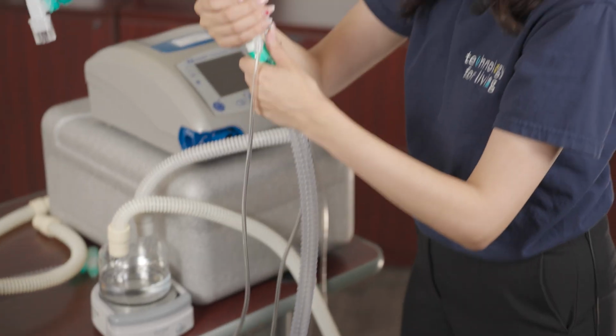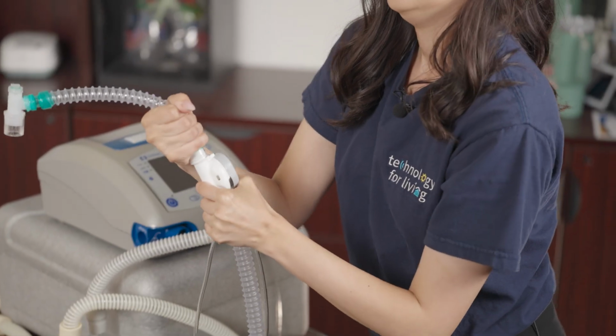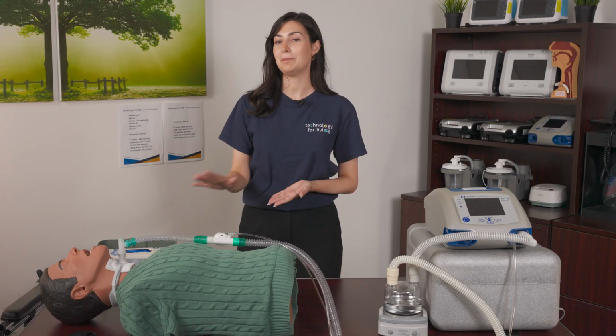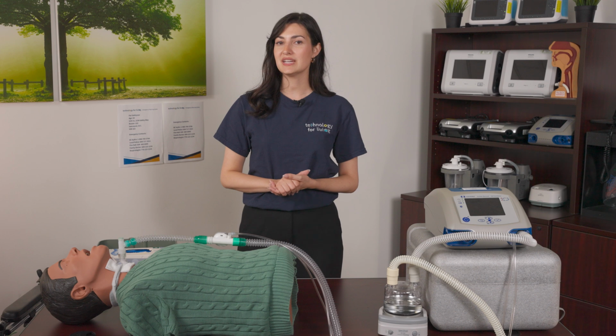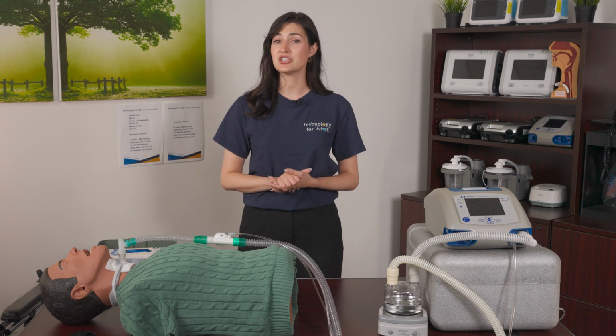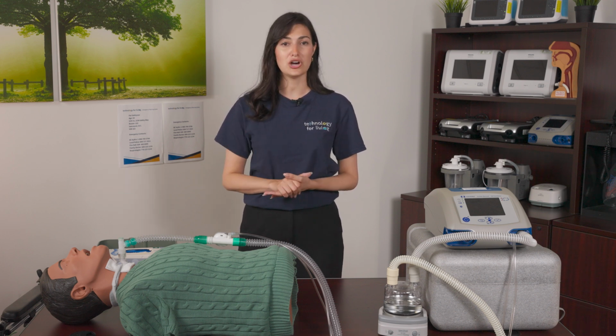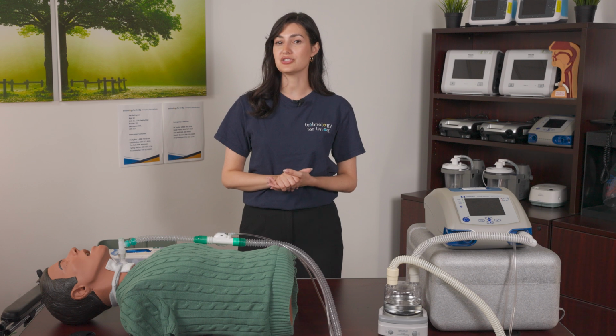I've addressed all the issues in the circuit, so I can now complete a circuit test and try the ventilator back on the member. Once reconnected to the ventilator, if the situation is resolved, then great. If not, try taking a brand new full circuit out of the package and attach it directly to the ventilator. If this still doesn't work, call PROP and speak with a registered respiratory therapist. They'll be able to assist you further and troubleshoot with you because the issue may be with the ventilator itself or with the exhalation valve and associated wires.